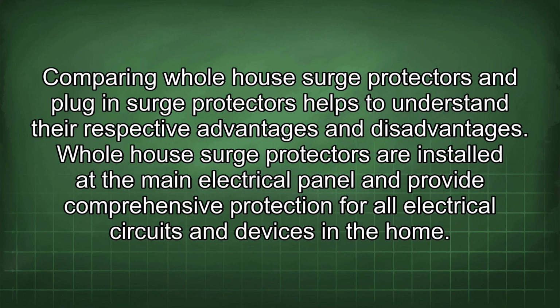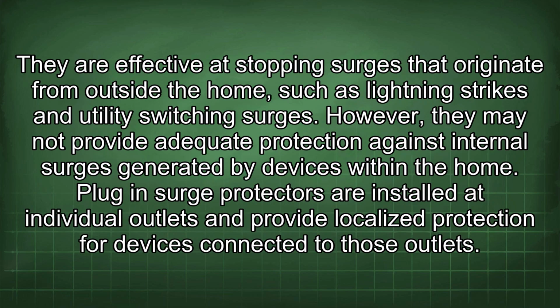Comparing whole-house surge protectors and plug-in surge protectors helps to understand their respective advantages and disadvantages. Whole-house surge protectors are installed at the main electrical panel and provide comprehensive protection for all electrical circuits and devices in the home. They are effective at stopping surges that originate from outside the home, such as lightning strikes and utility switching surges. However, they may not provide adequate protection against internal surges generated by devices within the home.